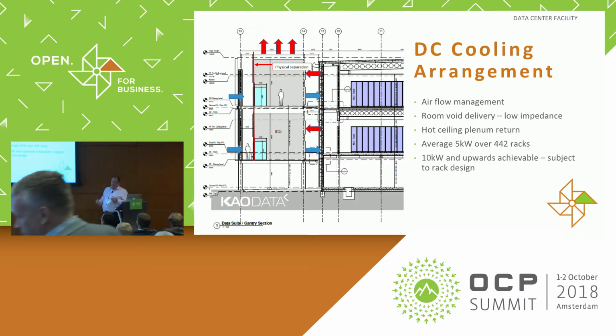A couple of things that does for us is that with all the equipment being outside, we can actually play to the strengths of the EU Code of Conduct, where equipment can be added as load grows. So you can start with 25-30% of the cooling equipment and grow as you fit out the IT. Generally, the way we've arranged the space is that we're based on 5 kilowatts per cab, but something we pick up as part of the monthly call with the Open Compute Foundation is looking at the trends for growing loads. And I think generally we're seeing that 10 kilowatts as being the mean. Yes, you get some up at 30, but ultimately, as long as the cabinet can take enough air through the front of the cabinet and cool, then our design will support those loads.